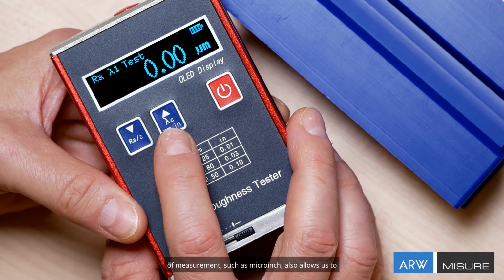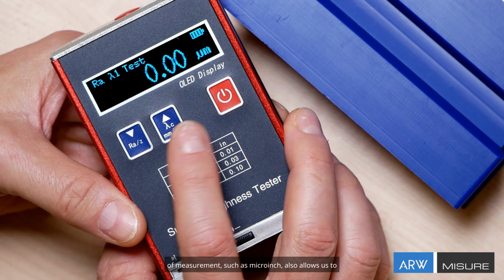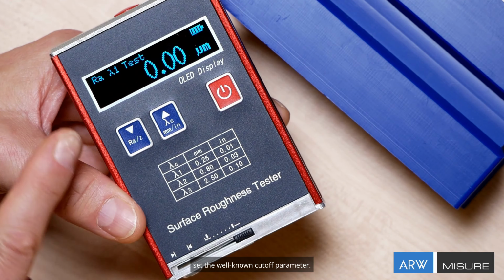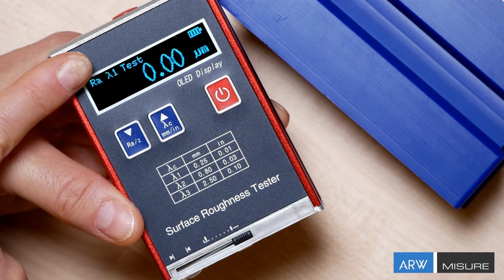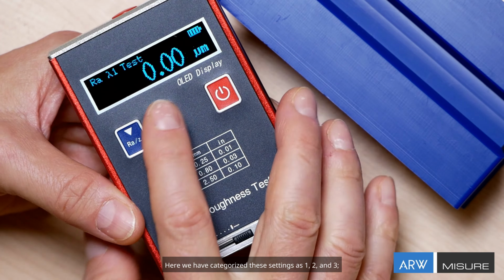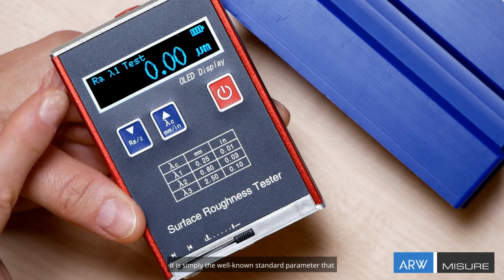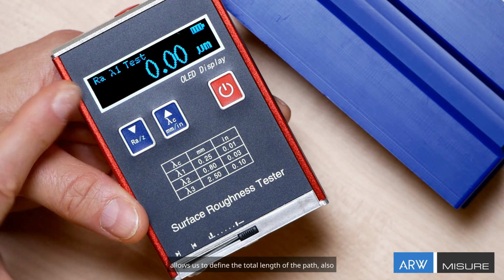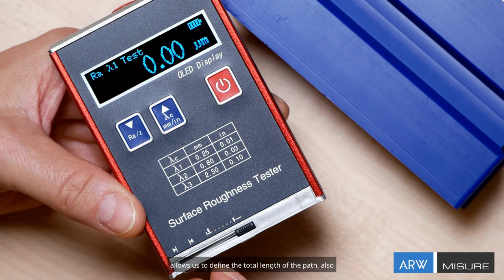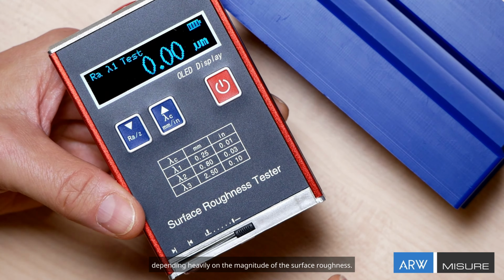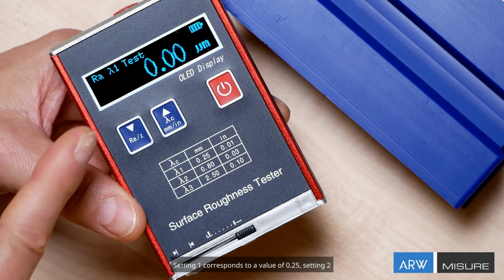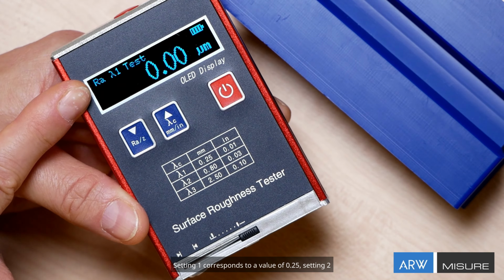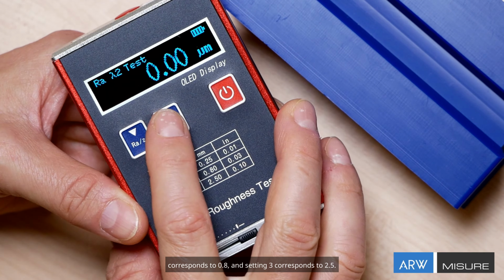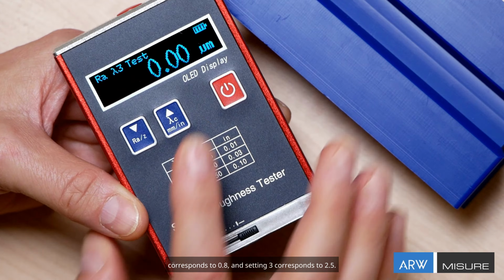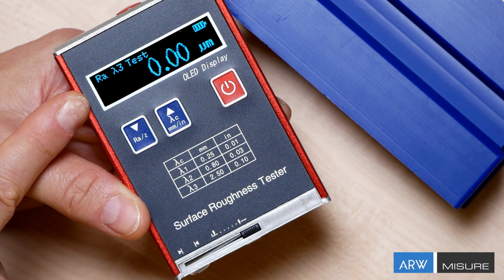The button next to it, in addition to setting the unit of measurement, such as micro-inch, also allows us to set the well-known cutoff parameter. Here we have categorized these settings as 1, 2, and 3. It is simply the well-known standard parameter that allows us to define the total length of the path, also depending heavily on the magnitude of the surface roughness. Setting 1 corresponds to a value of 0.25, setting 2 corresponds to 0.8, and setting 3 corresponds to 2.5.